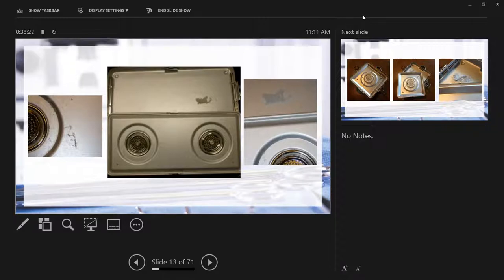The problem with this is it's a spring-loaded pan, so it's two lids in one lid, if you will. So when you pull these springs out, the internal lid will come out—it separates. But when it separated, look what I found: the dust. All this grimy dust was right there on the internal, and that was what I pulled off the shelf to get sterile instruments.